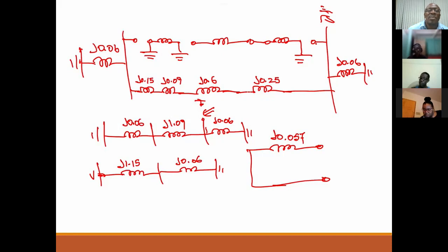Okay, so it can't be in per unit. So it's 5,855.6578 amperes, or 5.8556 kiloamperes, into the fault point. So let's take you through it then. Which networks did you connect?